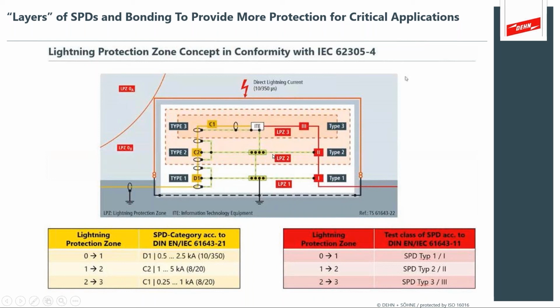A Type 2 device, which is actually similar to what's considered a UL type device, is ideal for downstream protection, where you're past the main service entrance. And I think those are some of the most important aspects you see between Type 1 and Type 2, which is the rating with a 10 by 350 microsecond pulse in the IEC methods.